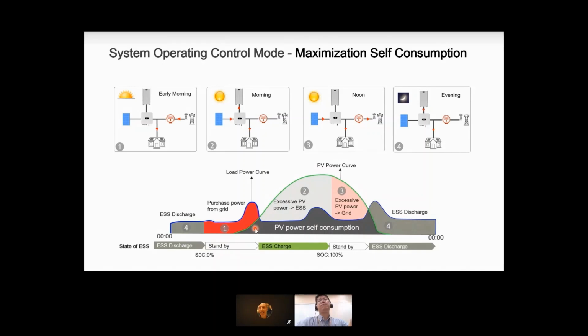So in the daytime, firstly, the PV power will provide power to the home loads. All of this load consumption will be met fully by the PV power. Excess PV power will be charged into the battery to charge your ESS system to 100%. Once the battery is fully charged, and if we still have excess power, then this power can be fed to the grid to make some extra money.